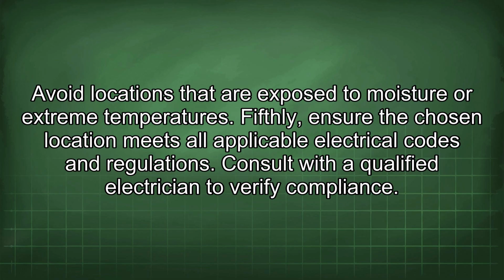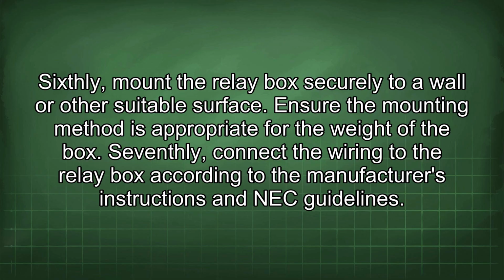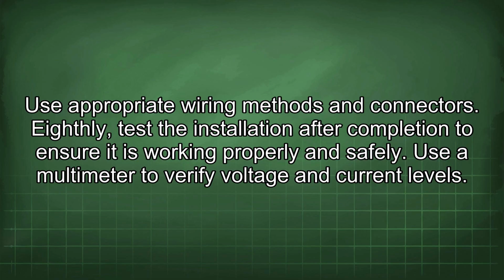Fifthly, ensure the chosen location meets all applicable electrical codes and regulations. Consult with a qualified electrician to verify compliance. Sixthly, mount the relay box securely to a wall or other suitable surface. Ensure the mounting method is appropriate for the weight of the box. Seventhly, connect the wiring to the relay box according to the manufacturer's instructions and NEC guidelines. Use appropriate wiring methods and connectors. Eighthly, test the installation after completion to ensure it is working properly and safely. Use a multimeter to verify voltage and current levels.